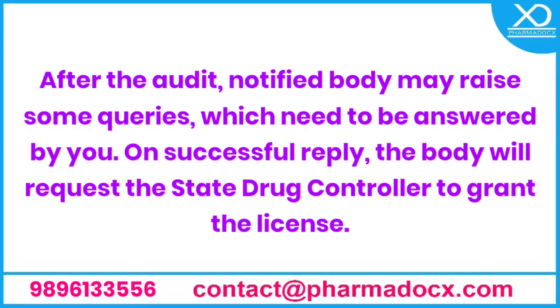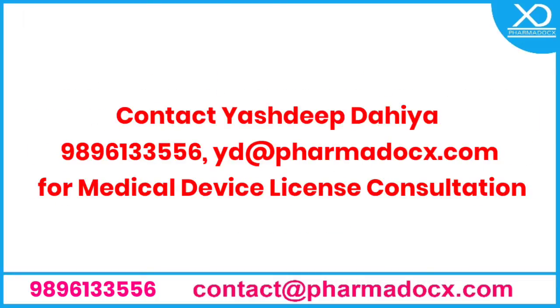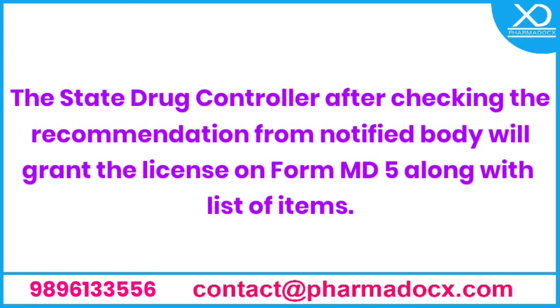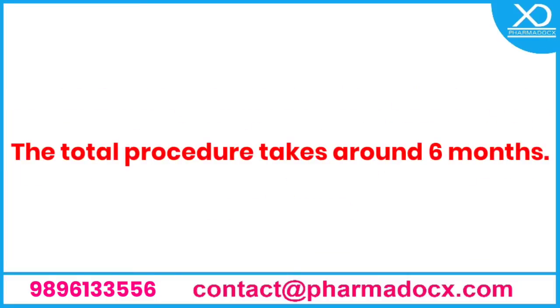After the audit, the notified body may raise some queries which you have to reply to. On your successful reply, the notified body will recommend grant of license to the state drugs controller. The state drug controller, upon receipt of the recommendation by the notified body, will issue the license on Form MD5 along with a list of items. This whole procedure takes around 6 months.